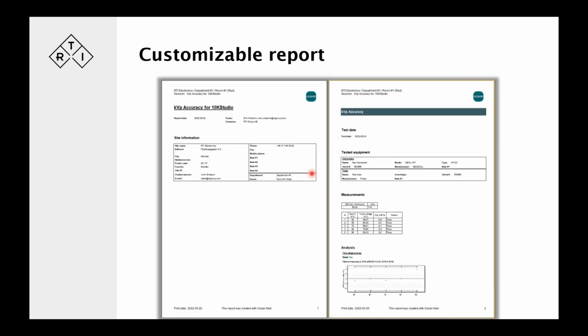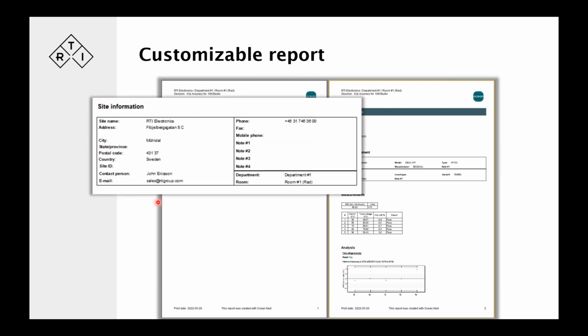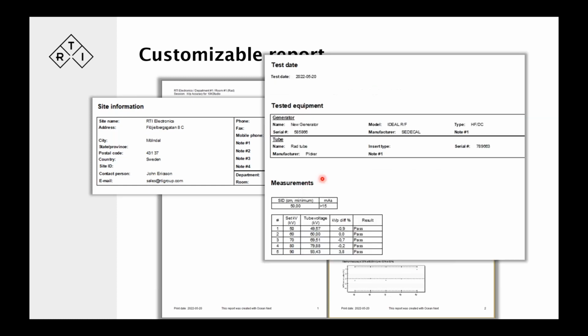If we have a preview of the report, this is what it says. So we have some site information that we had before. This is RTI Electronics and where we are. It's department number 1, room 1, fine. And in room 1, from the database, it's picked out that the generator is an Ideal RF from Sedecal. It's HF/DC, so serial number. The tube has a serial number of so much, and we also have the measurement values, the data from the measurement itself. So these are then default values that are available, and they can be customized in the report when it's done.